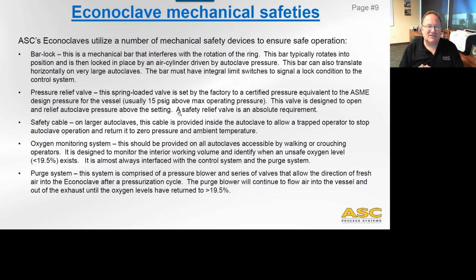So what mechanical safeties? Well, ASC autoclaves utilize a number of mechanical safeties that you obviously know about up to this point. I'm just going to run through them very quickly. The bar lock is almost one of the most important things, and that is the mechanical bar that interferes with the rotation of the ring. And this bar typically rotates into position, is locked into place with an air cylinder, driven by autoclave pressures. So when the bar moves in, autoclave pressure pushes that pin up and locks that bar and keeps that from being able to be opened.